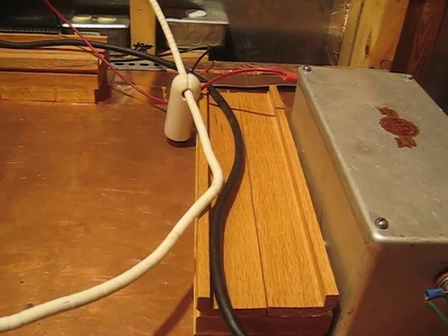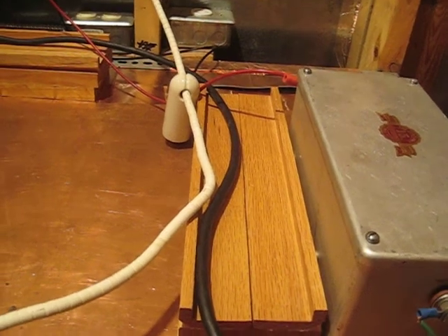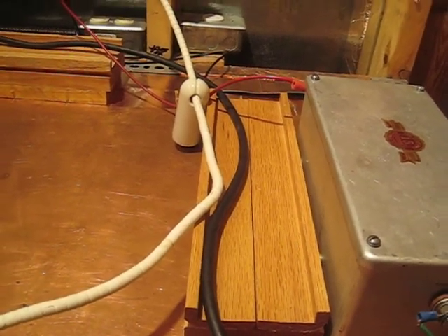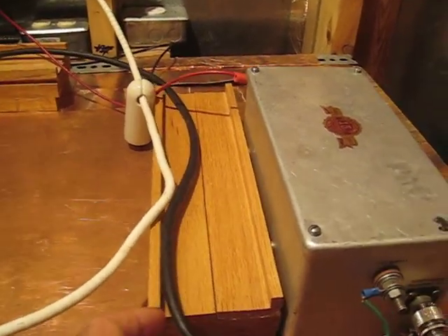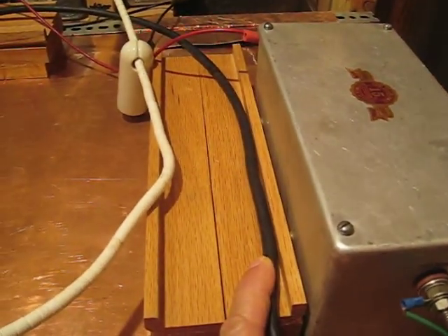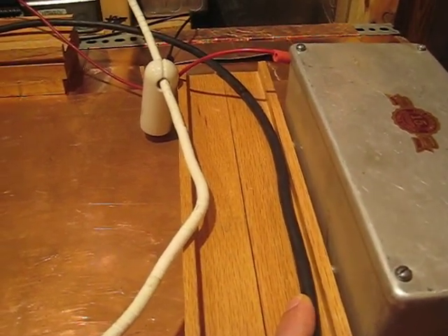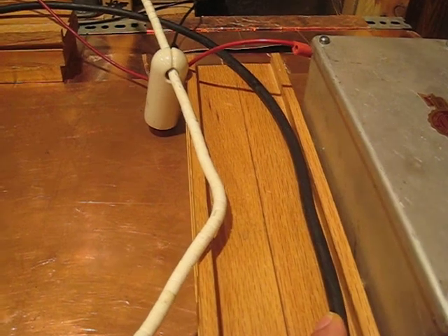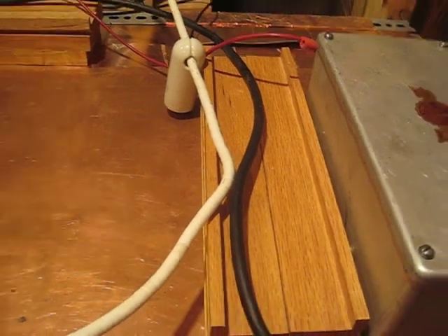In other words, we're actually getting into the front end, not through the power supply. So what I'm going to do here is I'm going to carefully reach in and pull the power away from the antenna, and we're going to listen for what happens as we pull that away. Okay. Just that much almost completely eliminated what we're hearing here. And if you'll notice, I pulled that, you could probably call that about 2 inches away. And if you'll recall that we have the requirement to separate different wires that are run together in the test setup by at least 2 inches. So there you go. Okay.